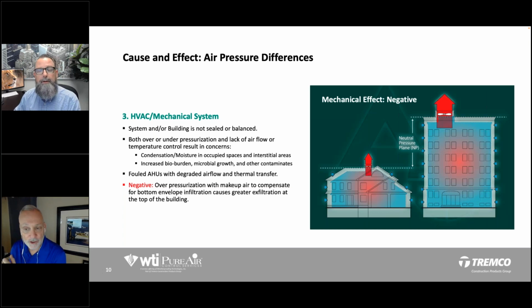Positive. So here we're showing negative pressure, and what's happening here is in this building we're exhausting so much, and maybe because the makeup air system is fouled, as you said, Troy, you're not getting the full pressure that you should. So the negative pressure is taking over, and you're pulling in from all sides of the building, through all the gaps, cracks, and holes.